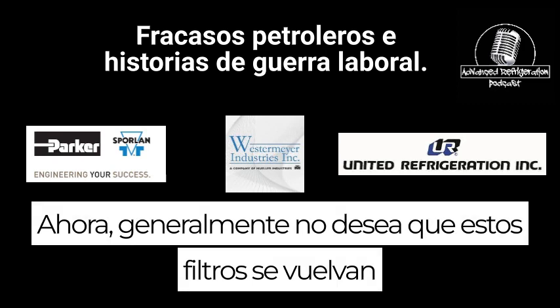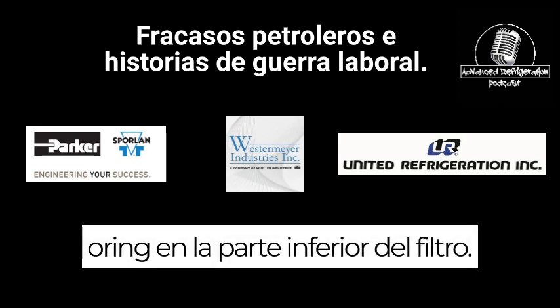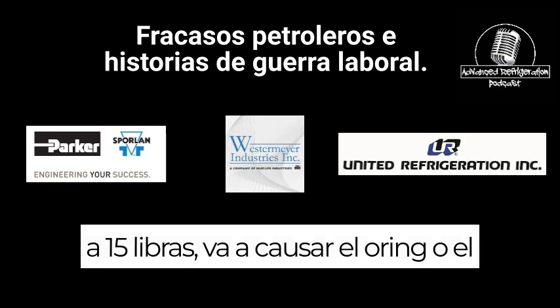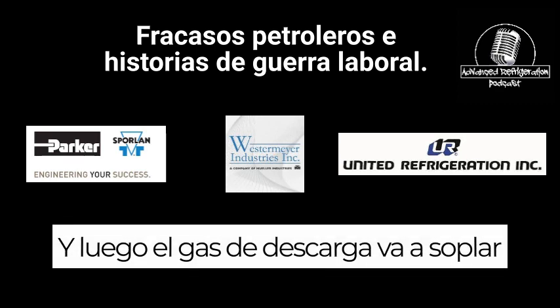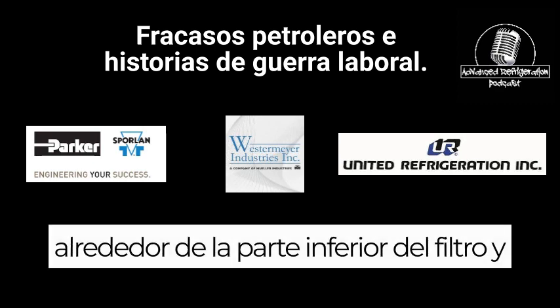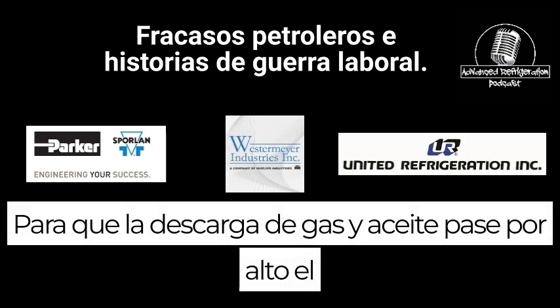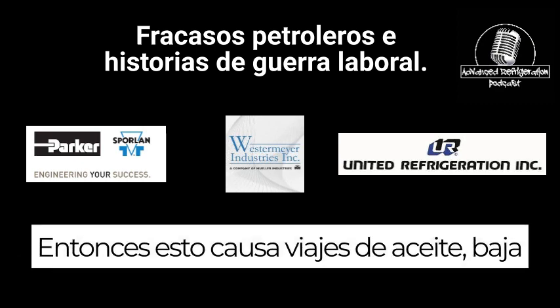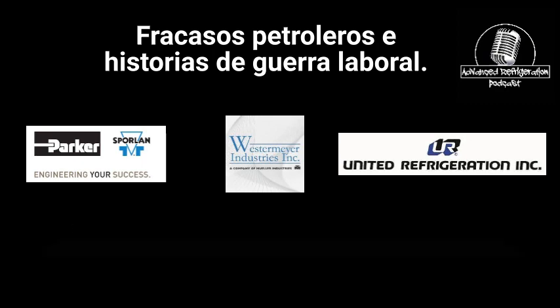Generally, you don't want these filters to get above 13 to 15 pounds differential or they blow the O-ring on the bottom of the filter. As the differential across the filter gets above 13 to 15 pounds, it's going to cause the O-ring or the gasket on the bottom of the filter to fail. Then discharge gas is going to blow out around the bottom of the filter and not go through the filter and aerate. So that discharge gas and oil bypasses the filter and goes out to the condenser. This causes oil trips and low oil production out of the separator. So this is something you need to look at.